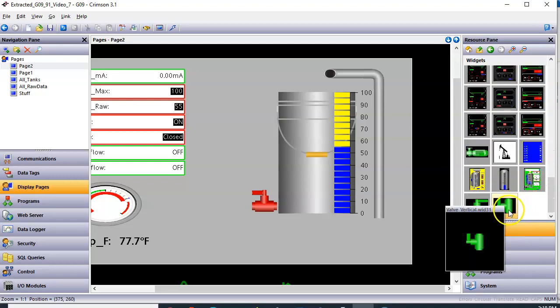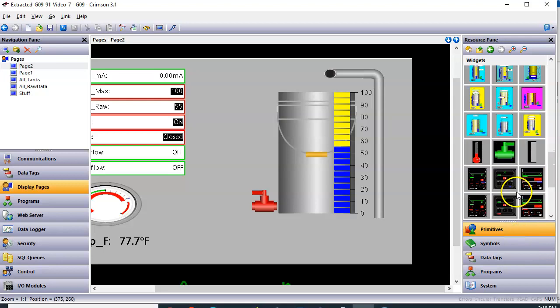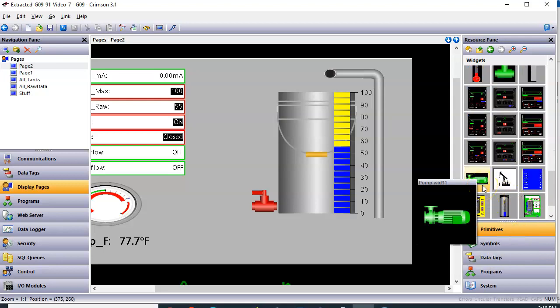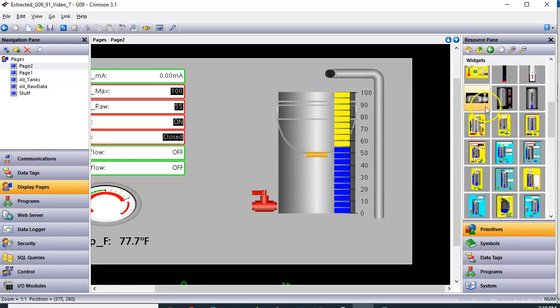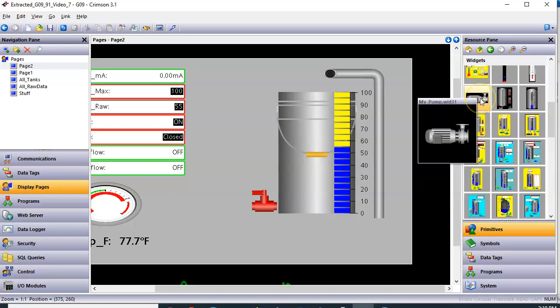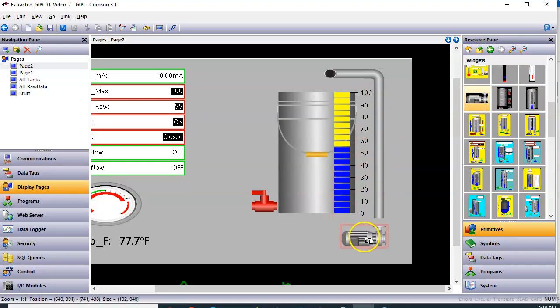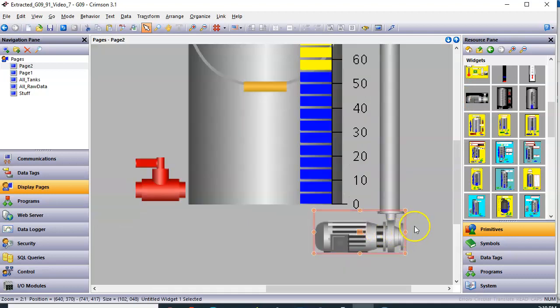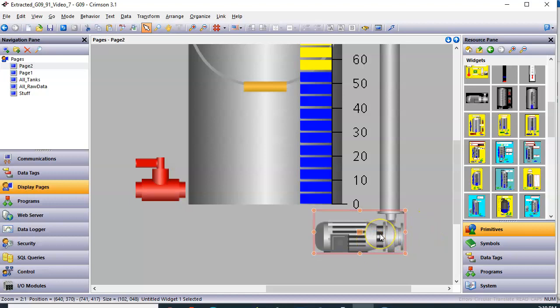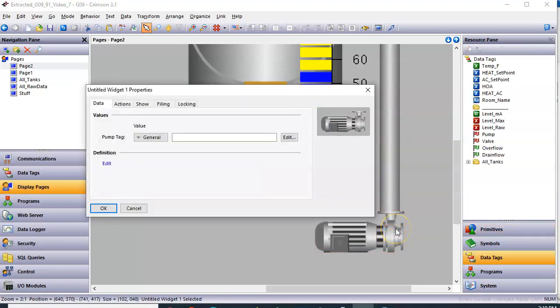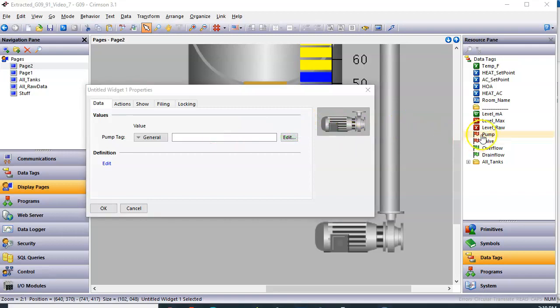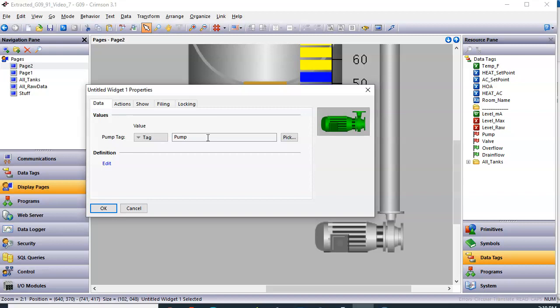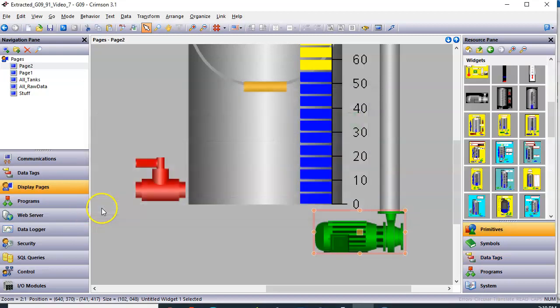So what you're going to do is you're going to drag this guy back out here, just like you had before. And I'll kind of just set it in the same spot. And then to reconnect this to the tag, all you got to do is right-click and go to Properties. And you're just going to grab the pump tag from here and put it right into here. So when I grab pump and drag it right here, that covered my action tab for there using pump. And it covered my coloring for this guy. So that's good. I'll click the OK button there.